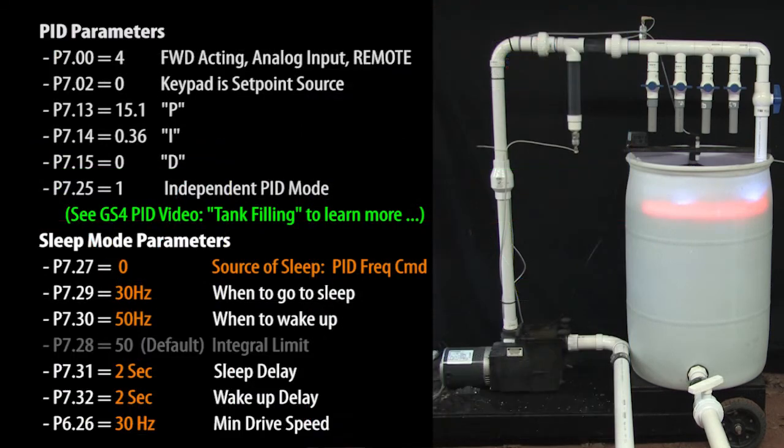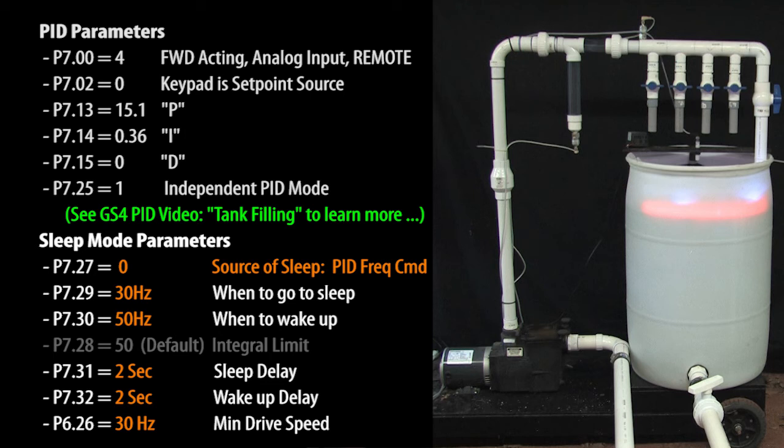One final note. PID is still running while sleep mode has the motor turned off. It can't do anything because the motor is off, but it is trying, which means the integral term is still integrating the entire time the motor is off. Now depending on your system, this can get quite large, which means it will take a long time for PID to settle out when the motor does get turned back on. If it is bad enough, the process can completely miss the set point and possibly create a huge miss.